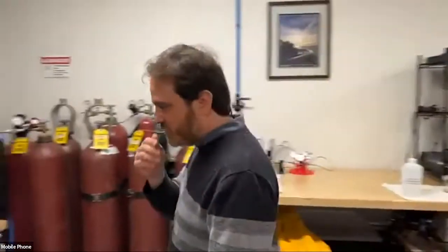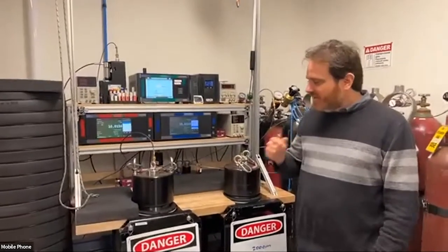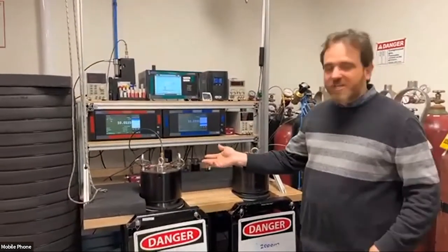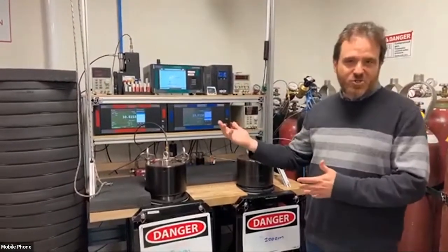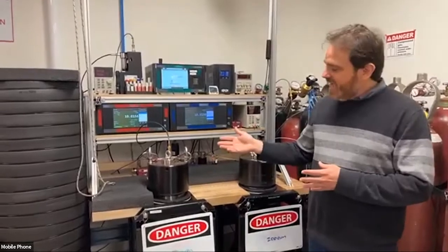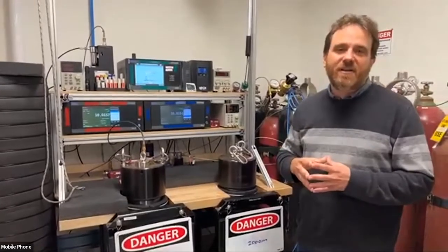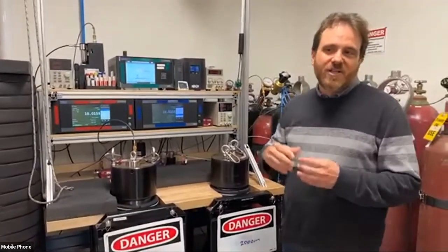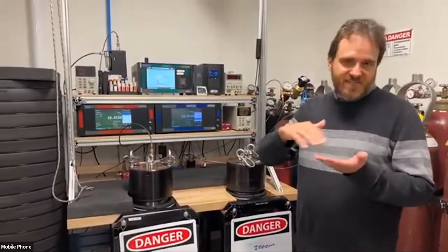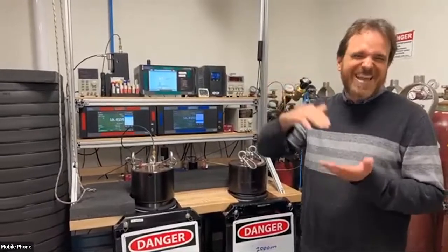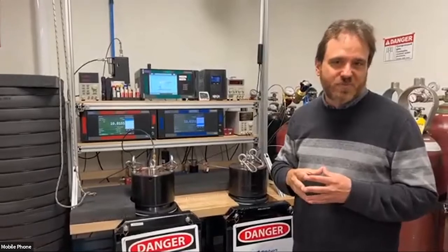So this is where we actually perform our pressure calibrations. The way we do this is we immerse our instruments into these pressure vessels, depending on the pressure rating of the instrument. And we run each instrument through a typically 10-point pressure calibration cycle. So if an instrument has a pressure rating of, let's say, 2000 dbar, typically we'll run 10 plateaus that are evenly distributed across the entire pressure range of the instrument.